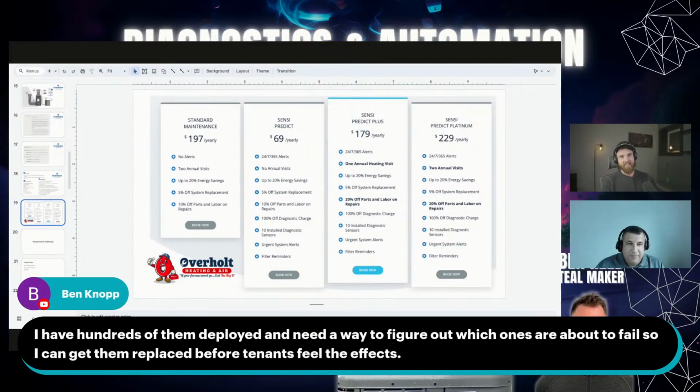I love the comment there about predictive maintenance with Fujitsu mini split leaks. This is one thing that we're going to have to face. We've got systems that hold a lot less refrigerant than they ever have, especially when A2Ls hit the market. And so the difference between the system performing at peak efficiency and not performing at peak efficiency is going to be a fly snot bubble's worth of refrigerant leak. If we can catch that early, then that is worth it. I think refrigerant leaks are going to continue to be a big thing, and it's going to take less time for them to impact the performance and efficiency of the units.